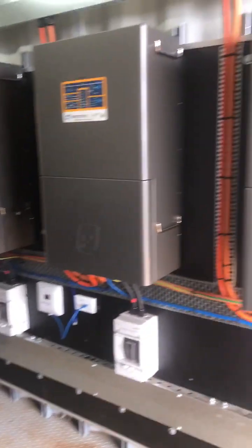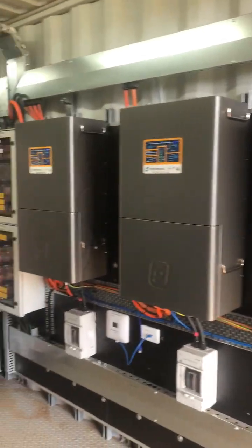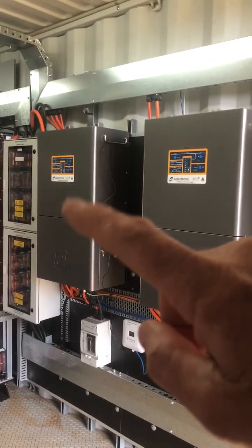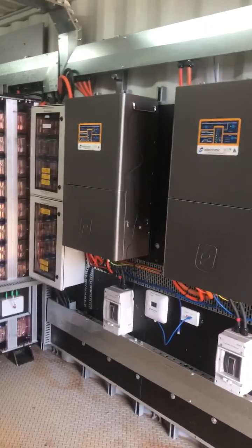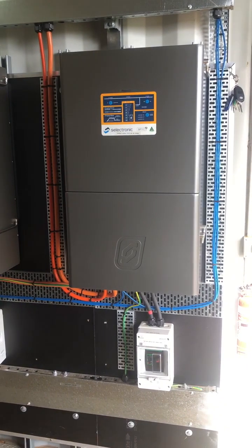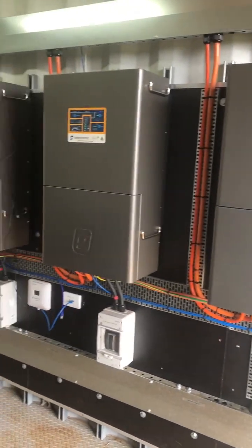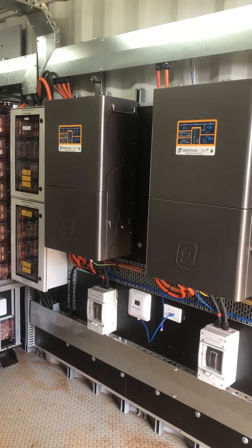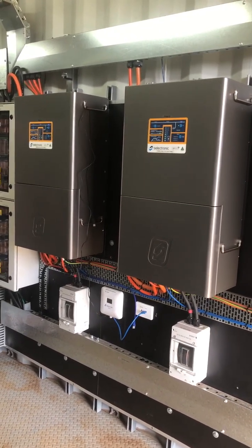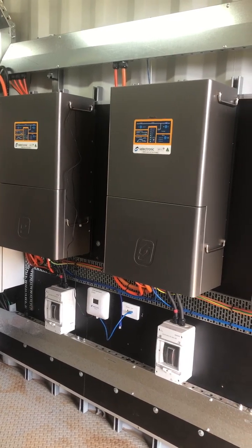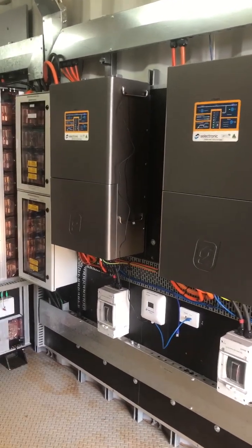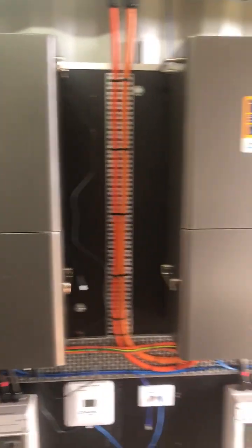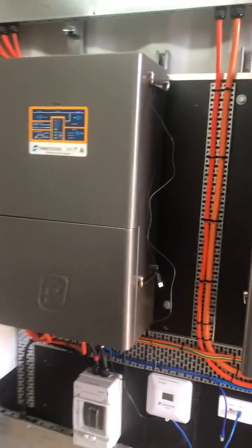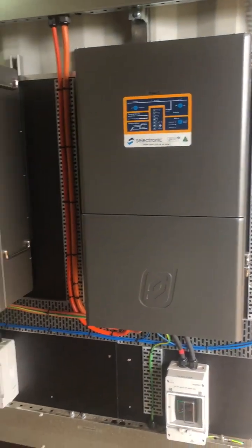Now on this side, these are what we call multi-mode inverters. Each of these inverters is a 20 kilowatt inverter. So basically over three phase we have 60 kilowatts of AC power that can go into the site at any one time. In fact, it could go up to 80 kilowatts if it needed to for about half an hour, because good inverters always have a fairly significant surge capacity. When you do this kind of configuration, one of the inverters is the master inverter, and it's generally phase A. So this is our master inverter, and these are what you might call worker inverters.